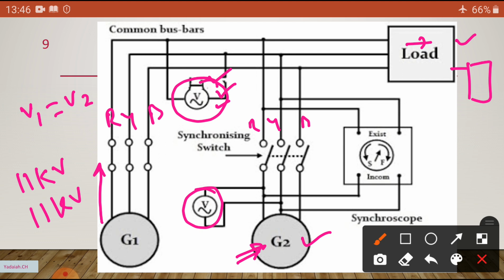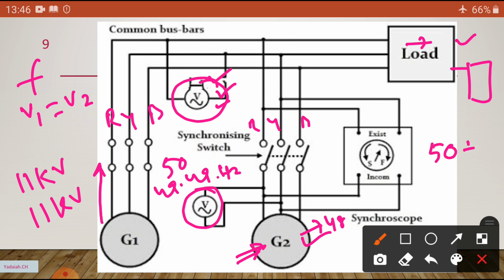Now I want to check the frequency. This frequency is 50 Hz, for example it is 49.49 Hz. Now the incoming machine may be 48 Hz. It is possible to connect. We have to check it because 50 Hz plus or minus 5% is the tolerance value.